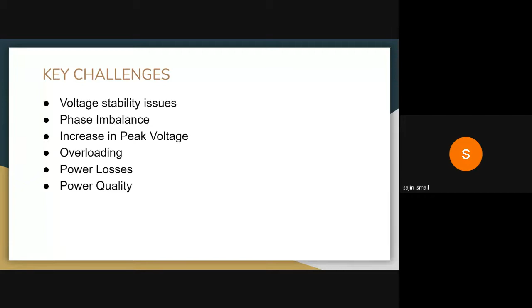So I'll start with the first issue: voltage stability. As we know, in distribution lines, the R by X ratio is normally high because the reactance value is lesser, so R by X ratio will be high. Due to this high ratio, distribution lines are more susceptible to voltage sags because of high power drawn. So whenever there is high power demand, these distribution lines show susceptibility to voltage sags.